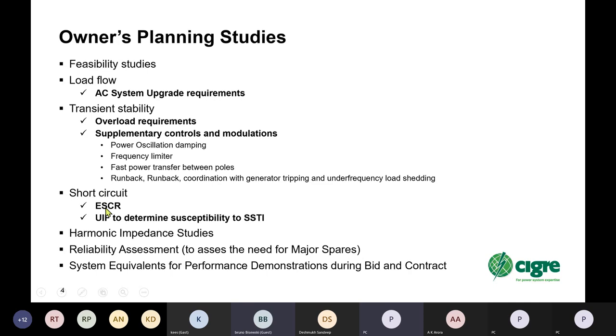Short circuit studies, that's to determine the equivalent short circuit ratio and get an idea of how well your DC, especially an LCC, will operate in the AC system, and to determine unit interaction factors, UIF, to determine the susceptibility to SSTI of certain generators in the system. And once they're identified, they can be studied in detail at the time that the DC is being designed.